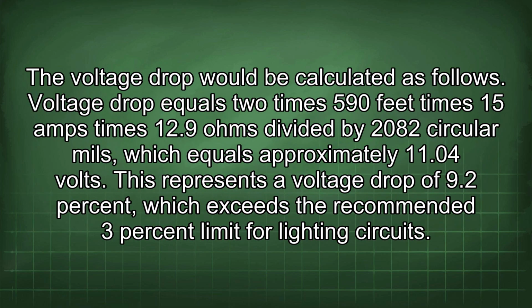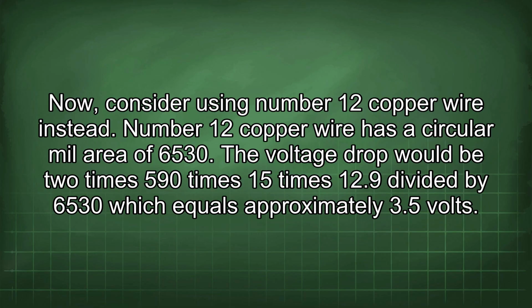The voltage drop would be calculated as follows. Voltage drop equals 2 times 590 feet times 15 amps times 12.9 ohms divided by 2082 circular mils, which equals approximately 11.04 volts. This represents a voltage drop of 9.2%, which exceeds the recommended 3% limit for lighting circuits. Now, consider using number 12 copper wire instead.